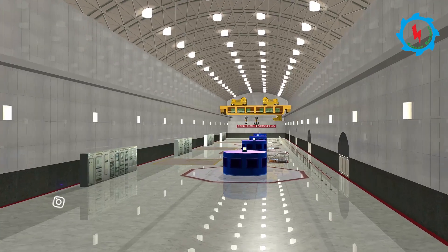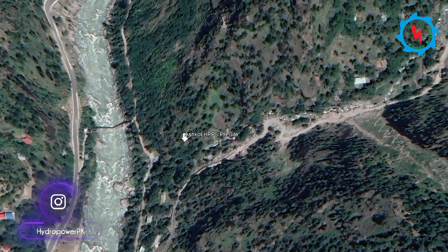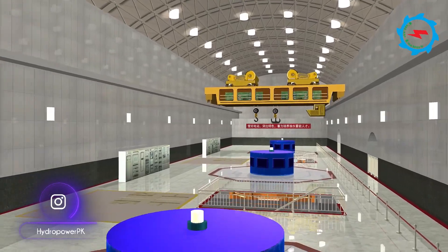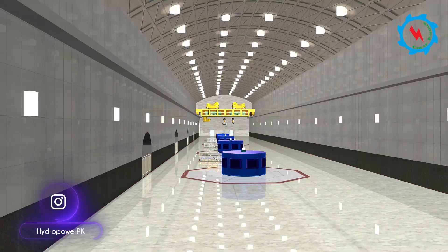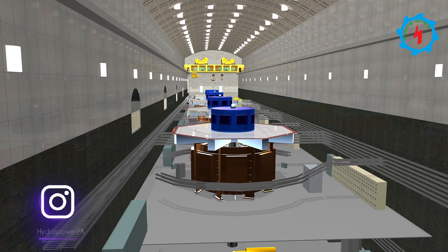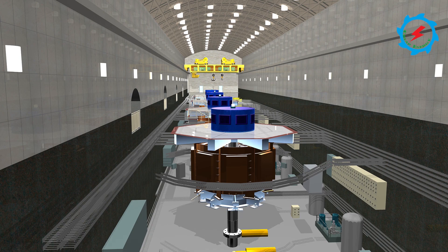The waterway system ends at a surge tank, which is followed by a penstock to transfer water towards the powerhouse. The powerhouse and transformer halls are designed underground on the left bank of the Neelam River, considering the geological conditions of the project area. The main machine hall would be equipped with five vertical shaft Francis turbines, each generating unit having 60 megawatts capacity.